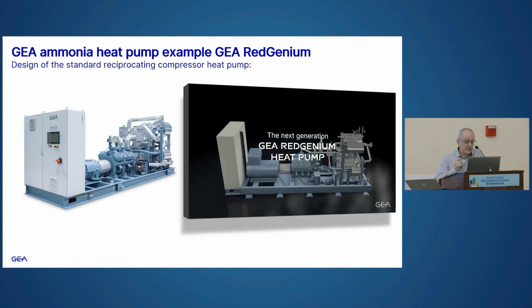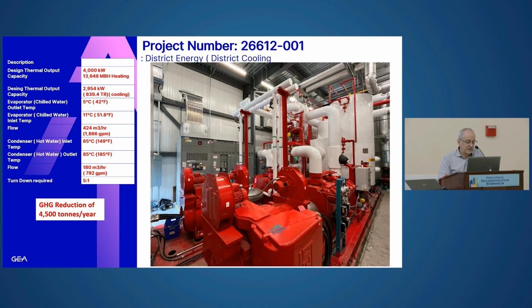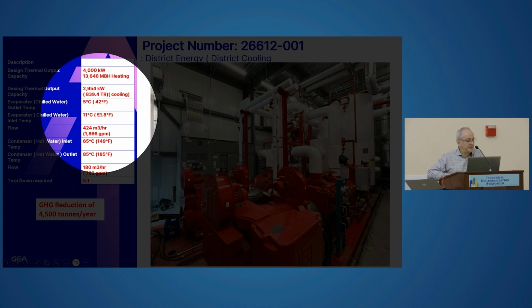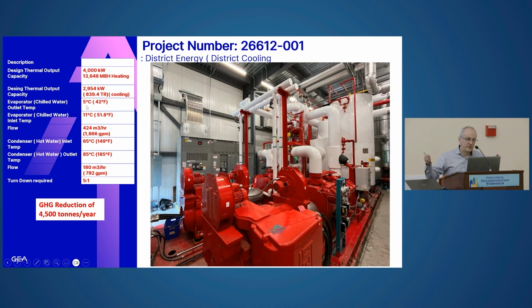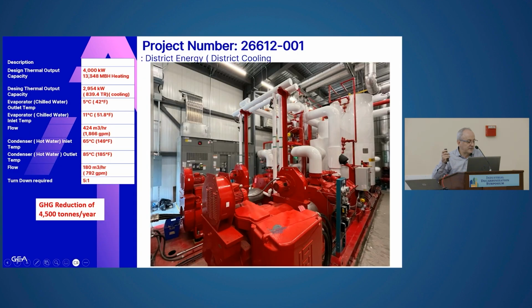A case like this is a district heating case. They do winter hot water for district energy, about 85C or 185F in the winter time, but also in the summertime they do 42F or 5C. So it's a combination of what they call district energy, district cooling, and district heating. This is in Markham, Ontario, in Canada. We delivered this last year, in summer 2023. It's already running and performing, and it's 4 megawatts: 2 sets, each one 2 megawatts, for a total of 4 megawatts heating capacity.